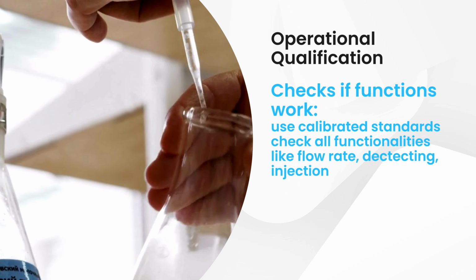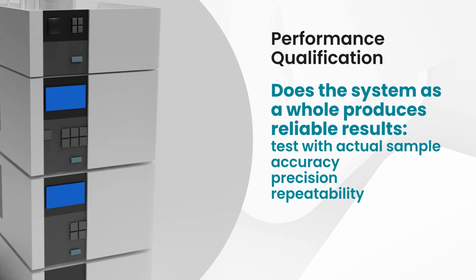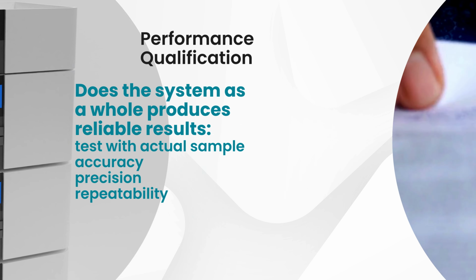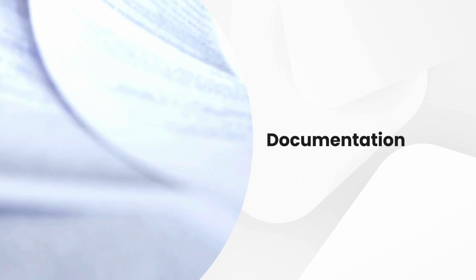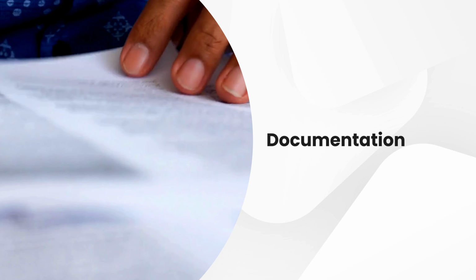Performance qualification. PQ is application specific. You'll use your actual samples and analytical method to demonstrate that the HPLC system consistently produces reliable results in your lab environment. This often involves analyzing known standards and assessing factors like accuracy, precision, and repeatability. Key considerations for successful HPLC qualification. Documentation. Meticulous record keeping is essential. Document every step of the process, including protocols, results, and any deviations.